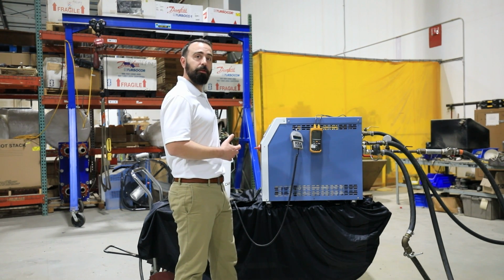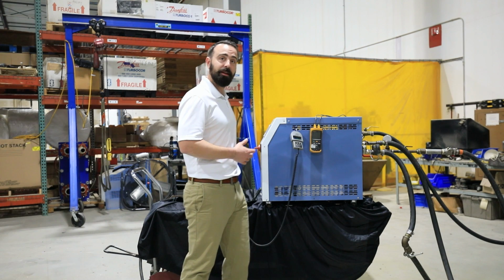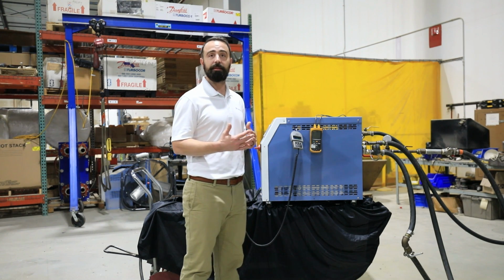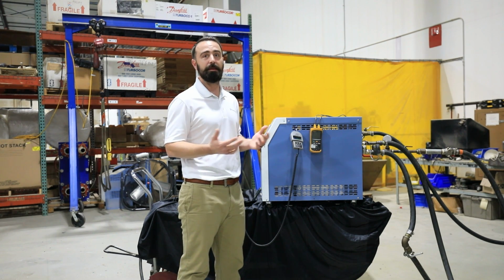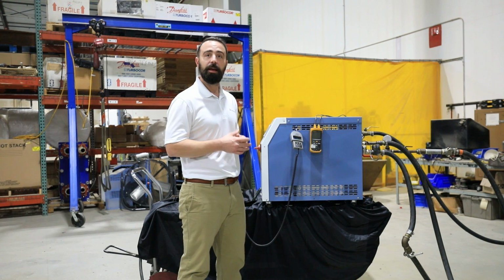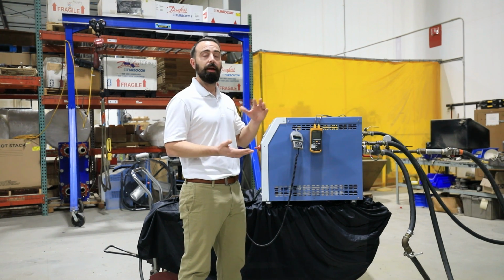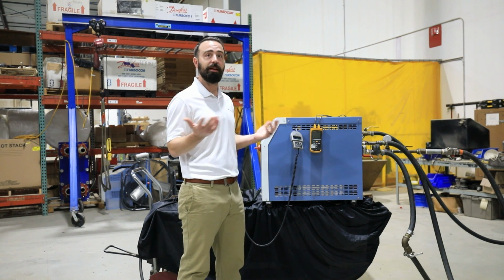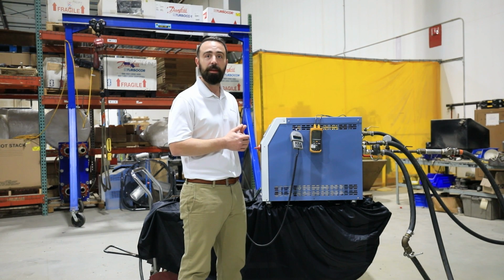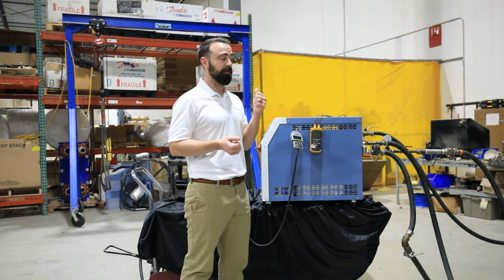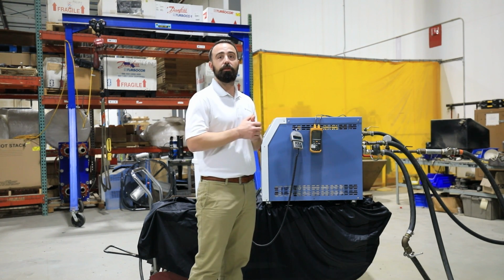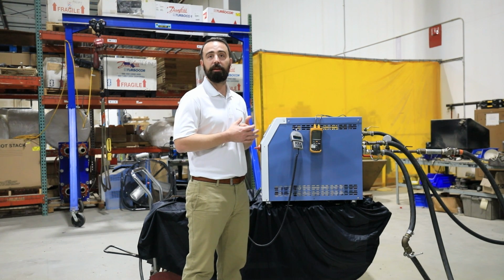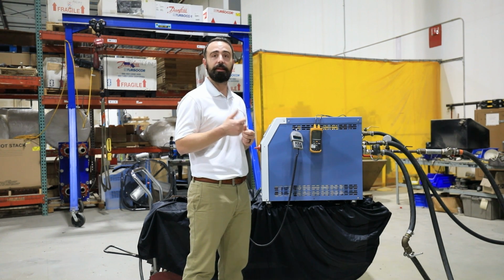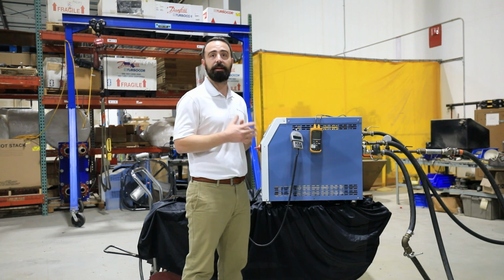knowing the difference between the empty bucket and the filled bucket in weight. We can use the weight of water at 8.33 pounds per gallon and determine the volume. And then with our timer, we can change that into gallons per minute. Using gallons per minute and your temperature differential, you can calculate the cooling requirement directly by multiplying the delta T by the GPM, and dividing it all by 24 to give you your tons of cooling.